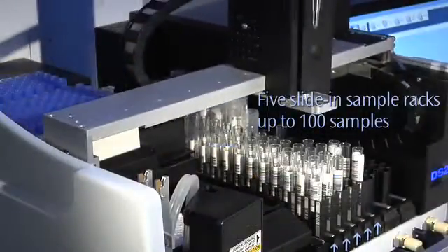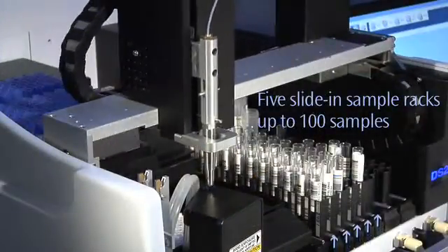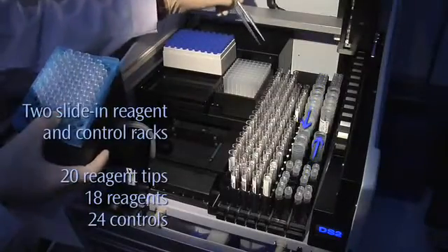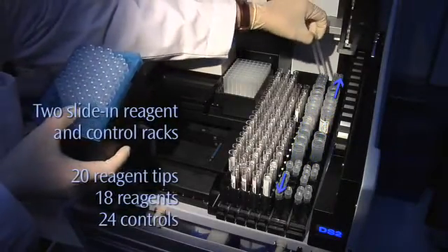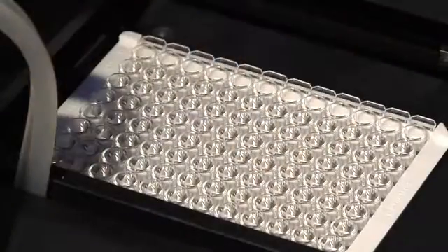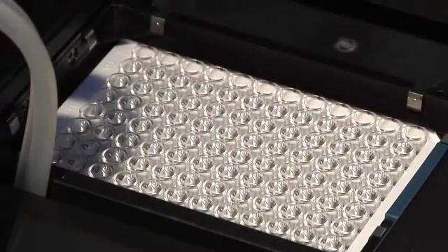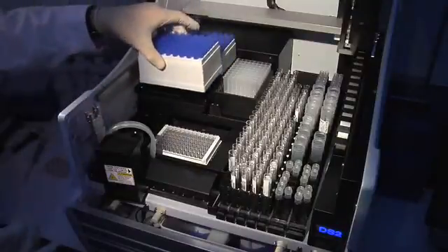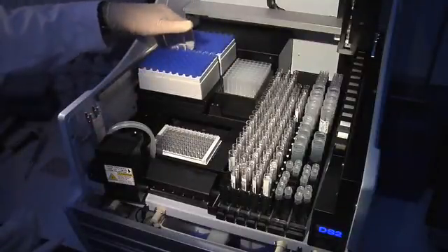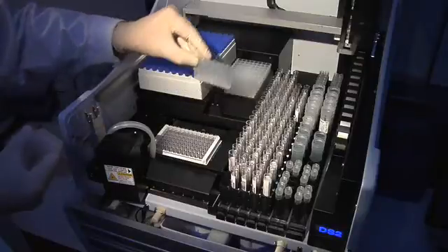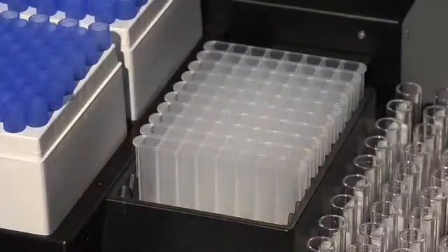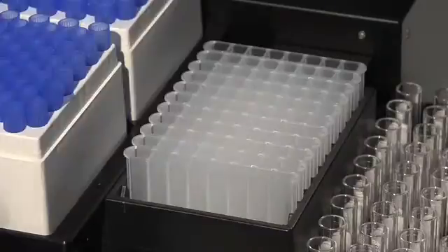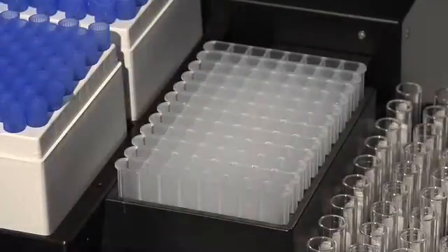Five slide-in sample racks hold up to 100 samples. The DS2 has two slide-in reagent and control racks for easy consumable access. An innovative multi-plate carrier holds two 96-well microplates. Two sample tip racks hold 216 tips total. The DS2 also features economical deep well strips, eliminating waste from having to discard partially used deep well blocks. Load only what you need for your assay run.